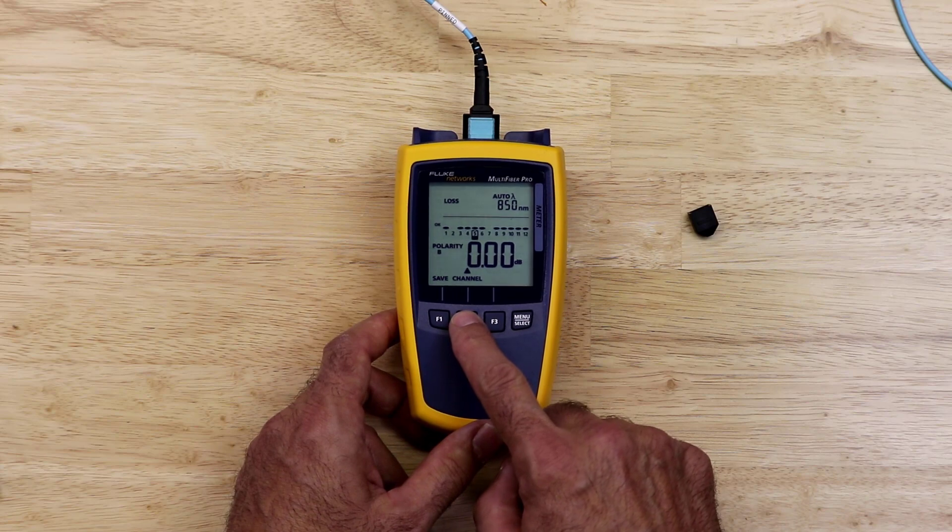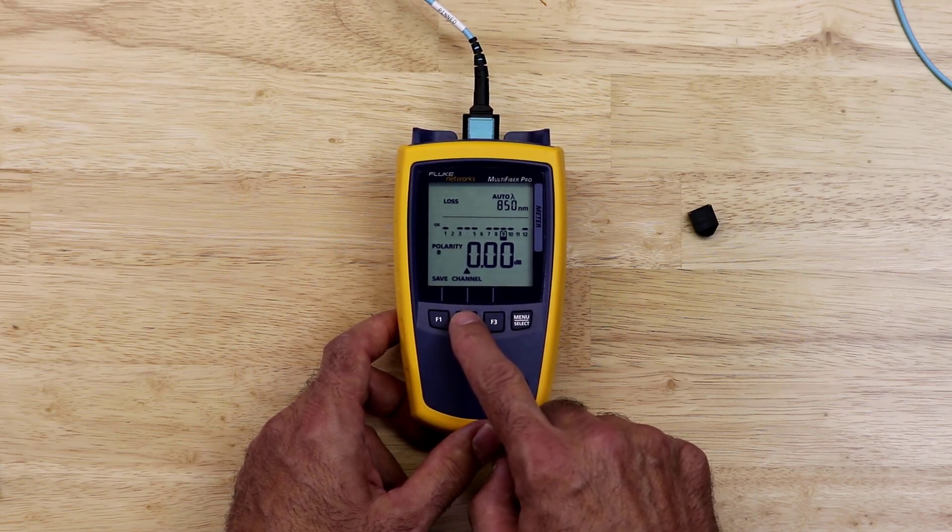If, after going through all of the channels, you see any loss, it's important to go back and reset reference. Values other than zero here could indicate that the light source did not have time to stabilize before setting reference. As long as we see values less than a few hundredths of a dB, we're good to start testing.